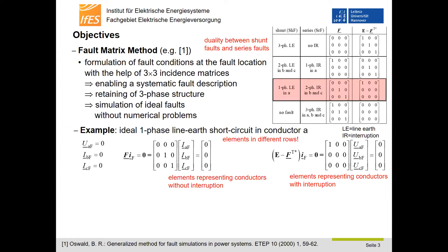The fault matrix is typical for each fault. Up to now, there is a duality shown between line-to-earth shunt faults and interruptions of electrical equipment with neutral grounding, as can be seen in the table on the right-hand side. The objective of this paper and presentation is the extension of the unified fault matrix method regarding a complete duality between shunt and series faults, in particular the duality between line-to-line short circuits and interruptions of equipment with isolated neutral.